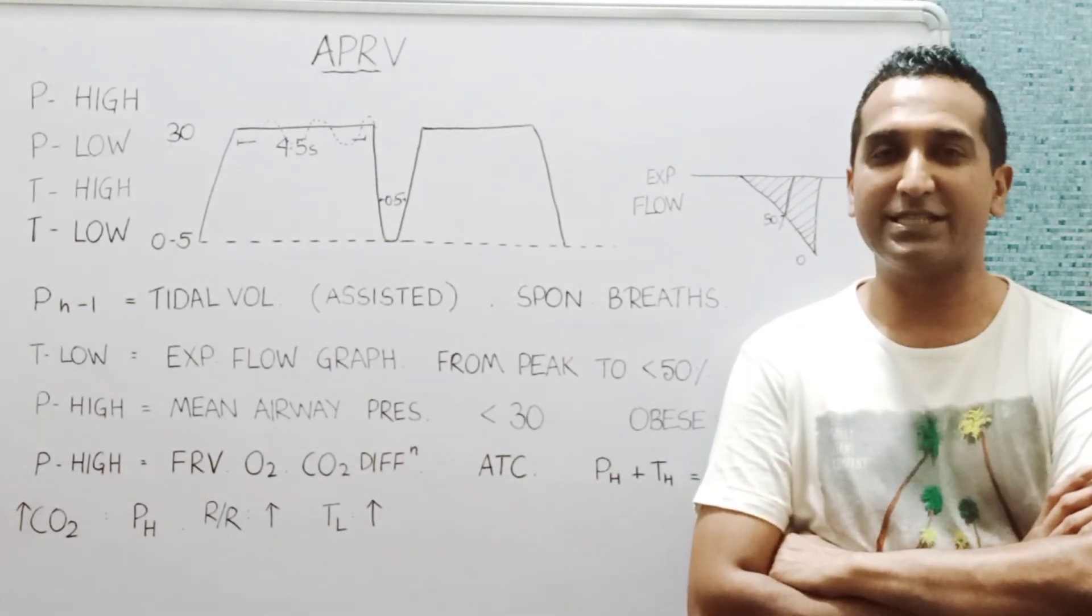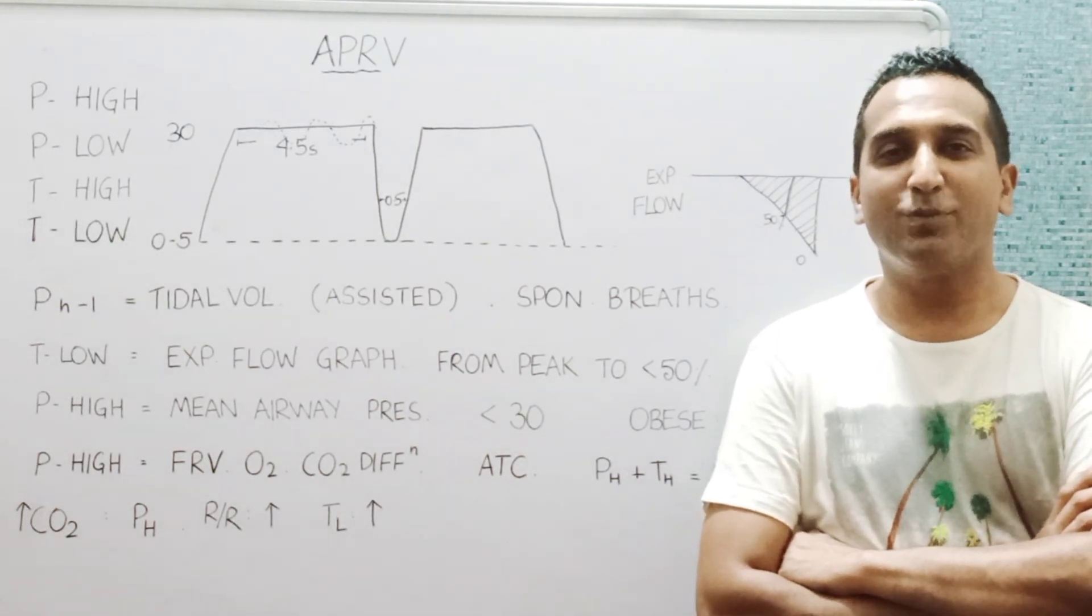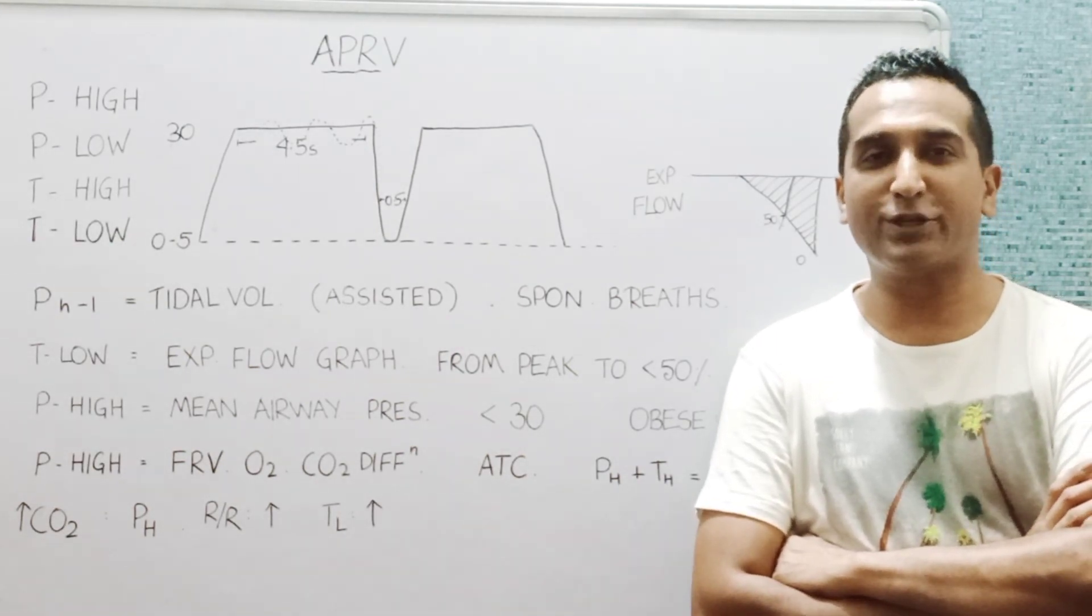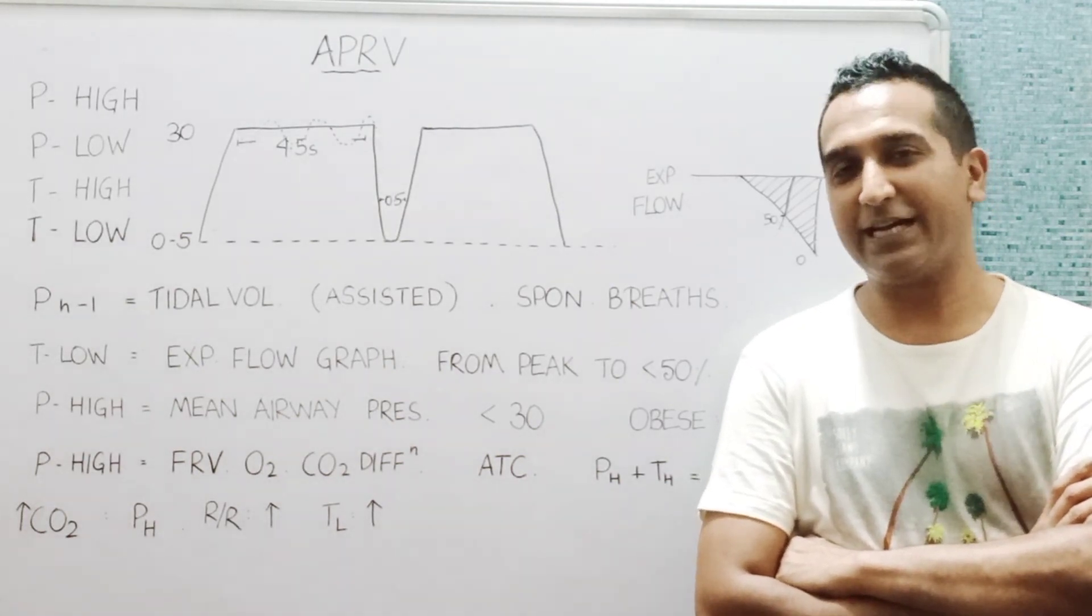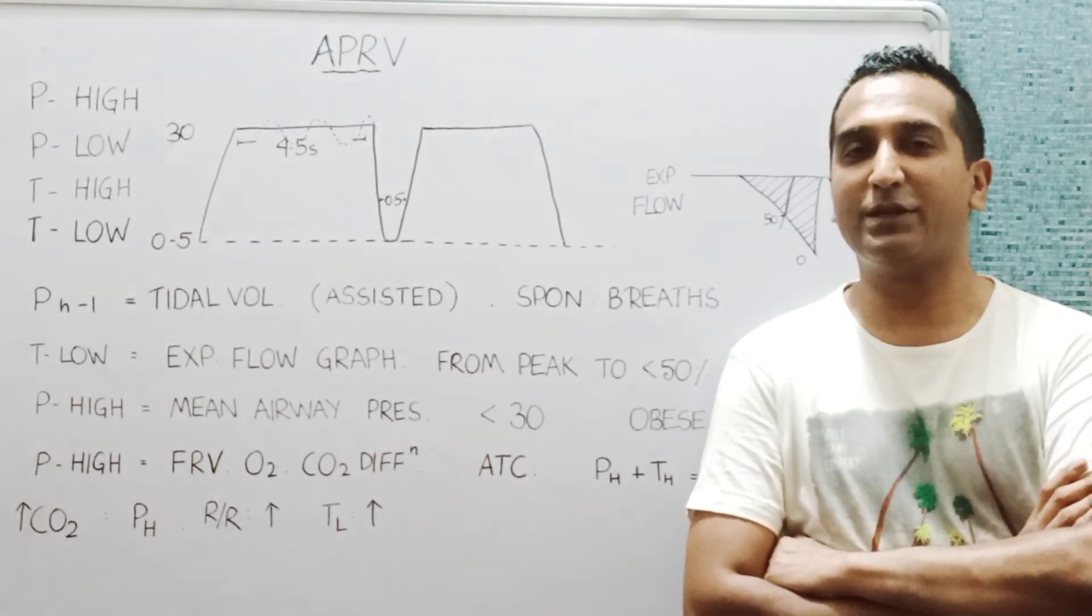You can consider it as a mode which keeps you at two different pressures, at a very high period of time at the higher pressures and a very low period of time at the lower pressures, and allows you to breathe spontaneously at those levels.